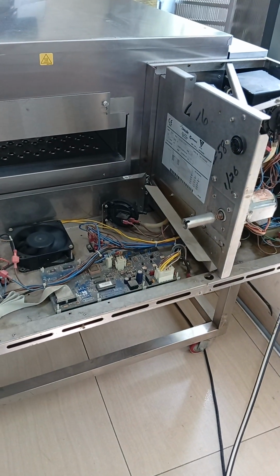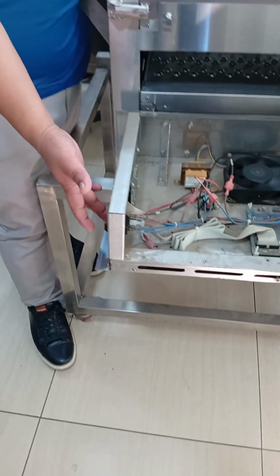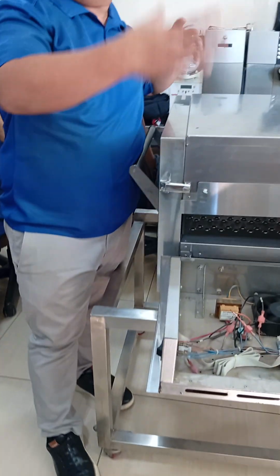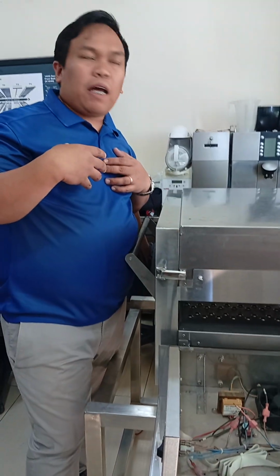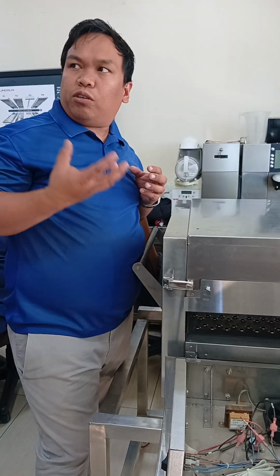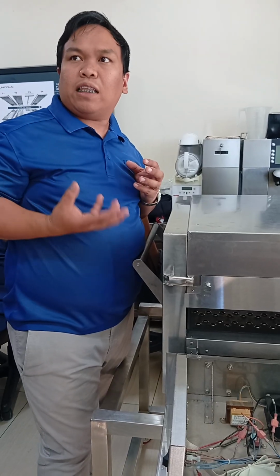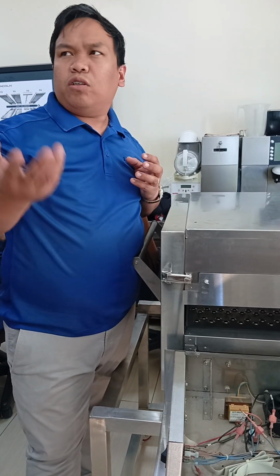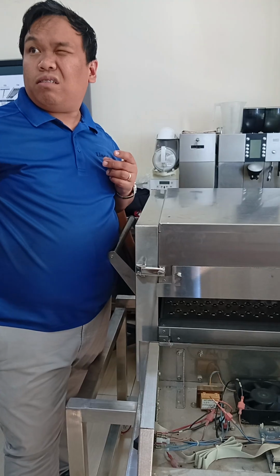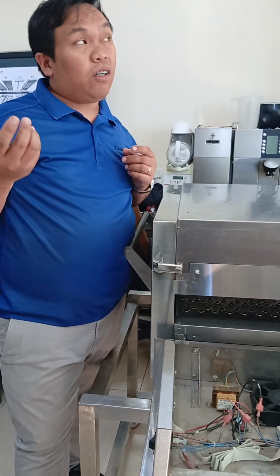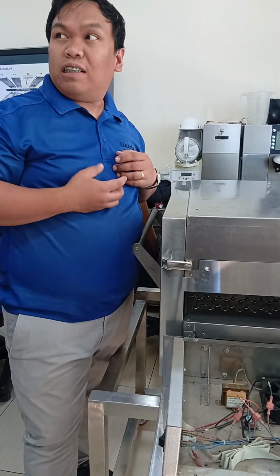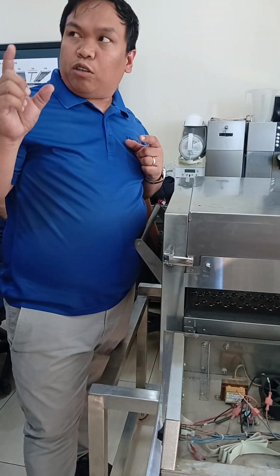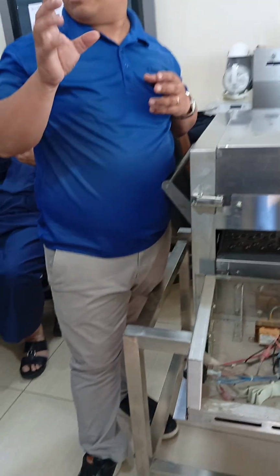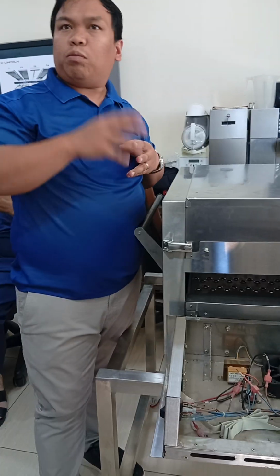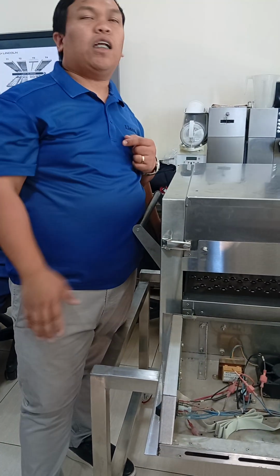Normally once you switch off here, the cooling fan will still work 12 to 15 minutes, at least until the temperature is below 100 Celsius. I don't know, in Fahrenheit it's around 200. But actually, the relay timing, to be exact, is 5 degrees Celsius below 100 degrees. Once below that, this will automatically turn off.